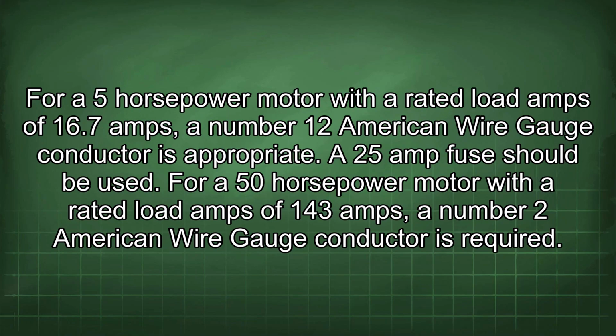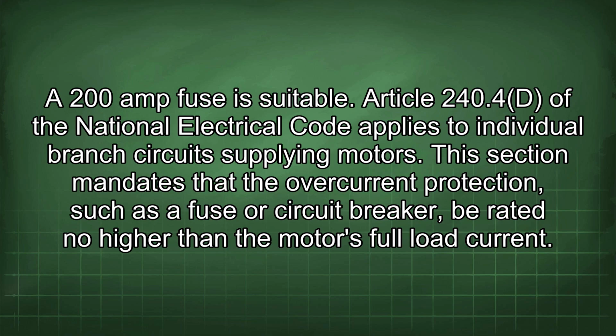For a 5 horsepower motor with a rated load amps of 16.7 amps, a number 12 American wire gauge conductor is appropriate. A 25 amp fuse should be used. For a 50 horsepower motor with a rated load amps of 143 amps, a number 2 American wire gauge conductor is required. A 200 amp fuse is suitable.